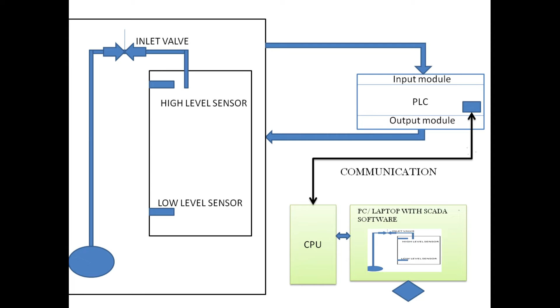Since the communication is made, whenever a low level sensor turns on, it will give a signal to the input module, right? So what will happen in the program is that I0.0 or any other address will turn on. Through that addressing, SCADA will get the update. So this animation will also do its work. If you have given the blinking option, it will blink. If you have given the color change, it will do the color change. So this is how we are able to supervise the field through the SCADA system. Got it? This process of monitoring the control system from the SCADA system is called a fully automated system.